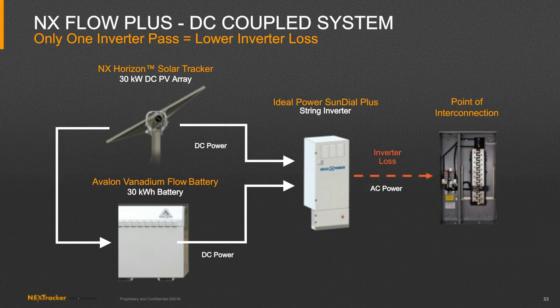You also recover clipping losses. By DC coupling the inverter - we're designers and engineers in the biz, we're used to doing like 1.3, 1.4, we've seen 1.5, 1.6 DC to AC design ratios - for the first few years before the panels degrade, that is completely lost revenue. We're able to recover that with the DC coupled system.